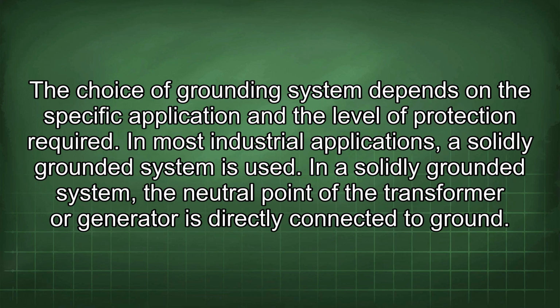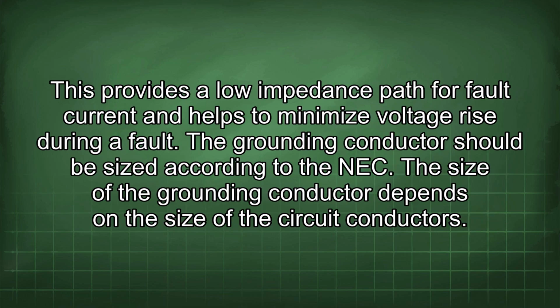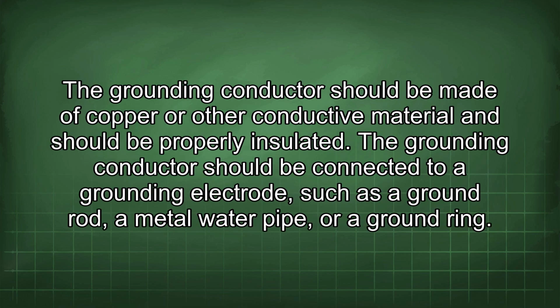In most industrial applications, a solidly grounded system is used. In a solidly grounded system, the neutral point of the transformer or generator is directly connected to ground. This provides a lower impedance path for fault current and helps to minimize voltage rise during a fault. The grounding conductor should be sized according to the NEC. The size of the grounding conductor depends on the size of the circuit conductors. The grounding conductor should be made of copper or other conductive material and should be properly insulated.